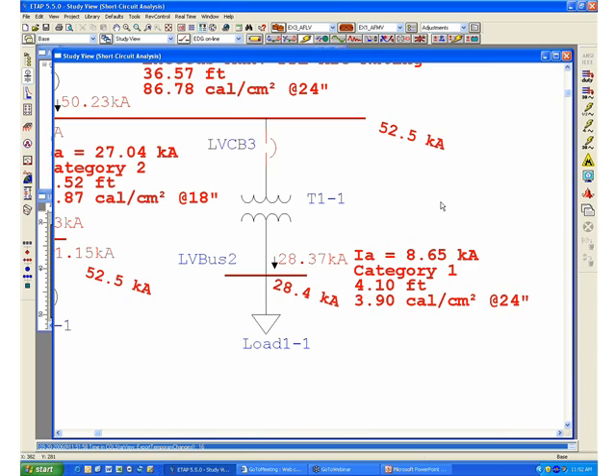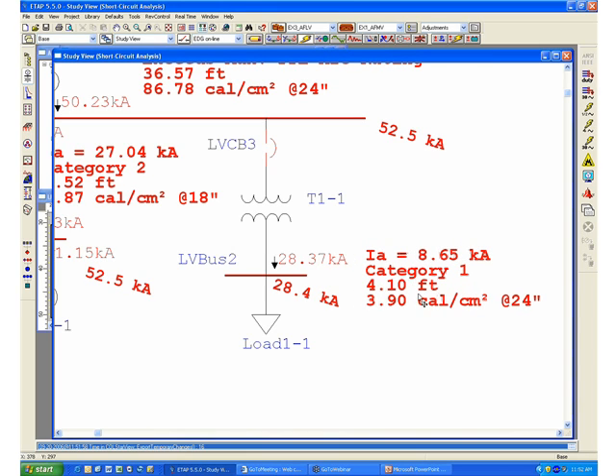we can rerun the study and observe that without the arc-current variation, the response of LVCB3 is actually much faster and you only have a category 1 fault level.